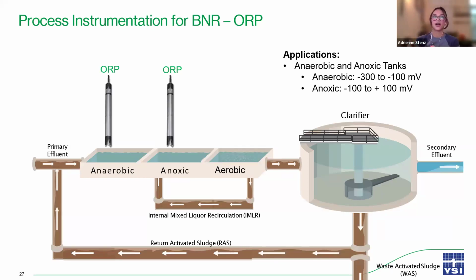Oftentimes, ORP sensors are used in anaerobic and anoxic zones. ORP stands for oxidation reduction potential, and ORP sensors measure the net balance of all oxidation reduction reactions going on within the process. So all of the nutrients that are removed from wastewater, BOD, ammonia, nitrate, phosphorus, these are all oxidation reduction reactions which involve the transfer of electrons between molecules, and ORP sensors basically measure the net balance of free electrons within an environment. I kind of like to think of ORP sensors as negative DO sensors.